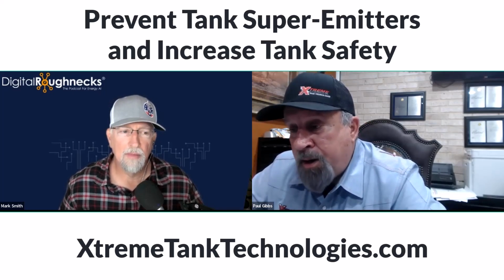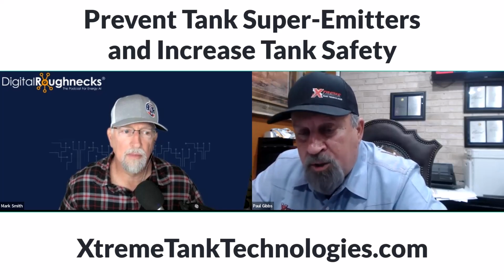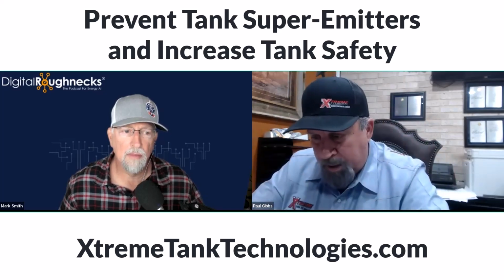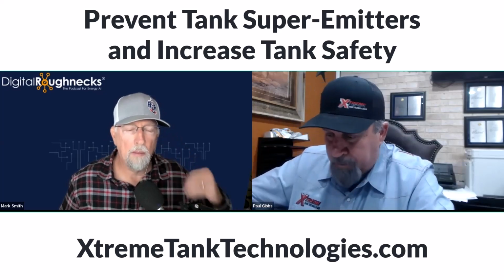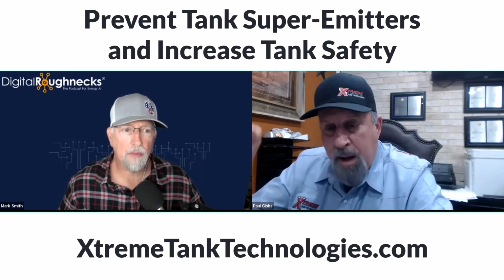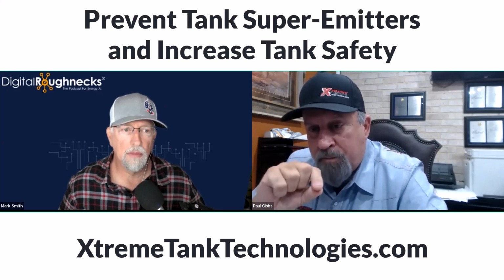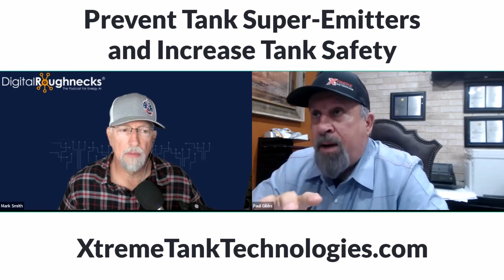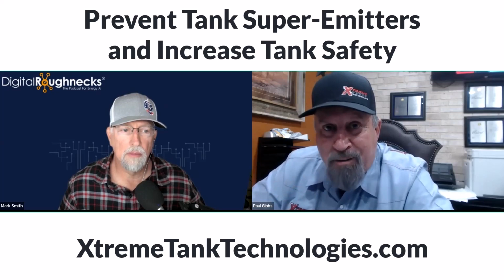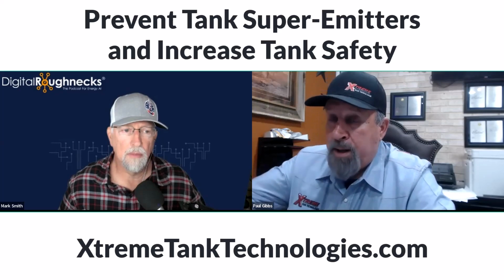I've even had cases here in West Texas where sweet crude oil was shutting them down at the gas sales meter. They have a GC analysis computer that runs everyone out here, and it will break it down and tell them how much of it: pentane, propane, methane. It breaks down CO2, oxygen, H2S, and it was shutting them off from H2S. They had a trace of H2S. Everyone does. It wasn't enough they had to worry about H2S. But the problem was H2S was the heaviest gas, and it was staying in the tank. It was not leaving, it was building, and it would build and build and build, and it would burp out when it got full enough.